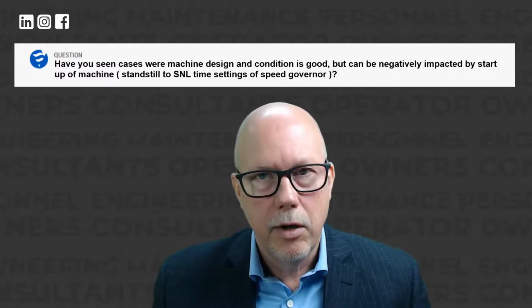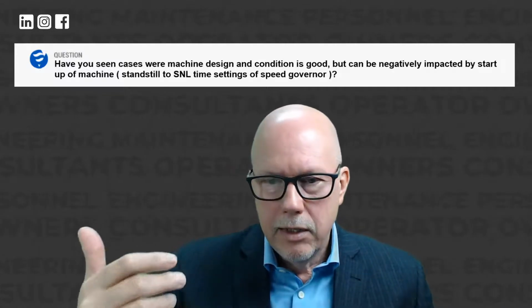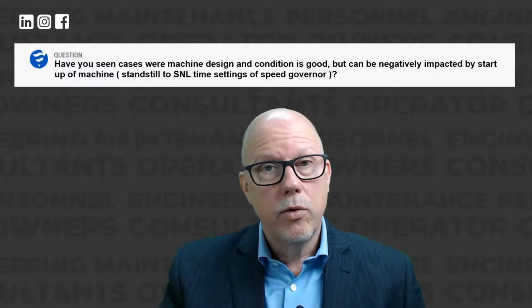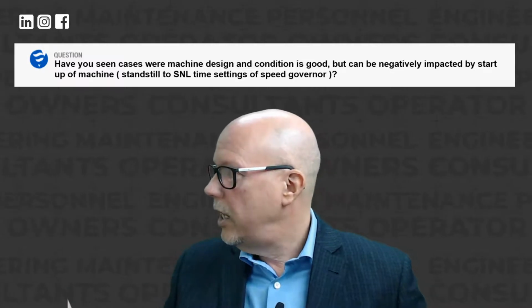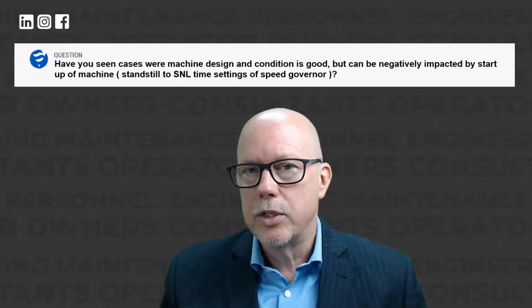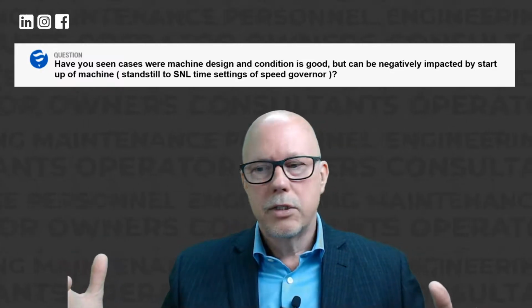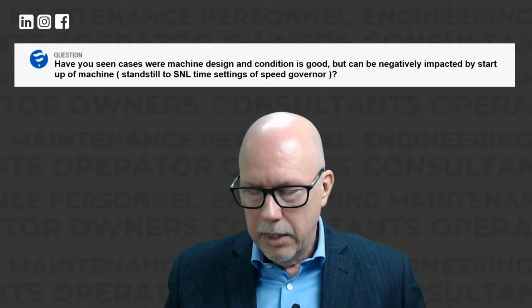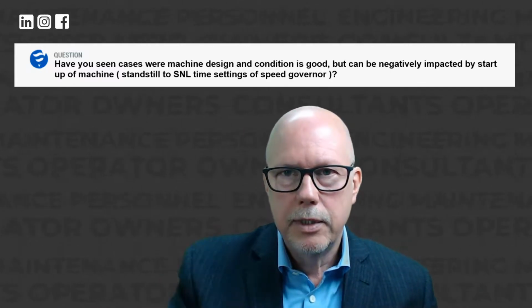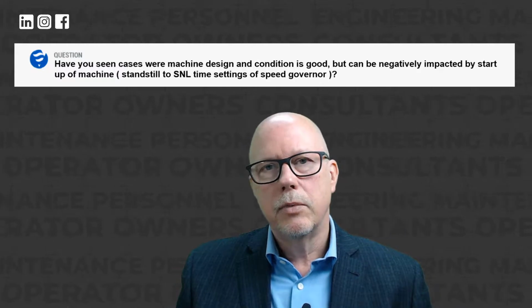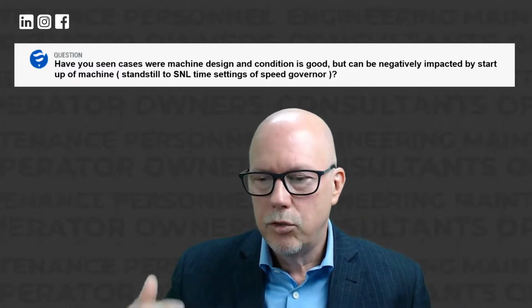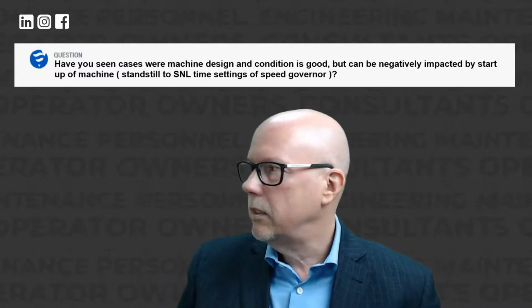So the unit was put through a tremendous amount of stress needlessly. It was just an error. If we hadn't taken the measurements and noticed this, it would have probably gone on unchecked, and eventually they would have had all kinds of rotor issues and wondered what the problem was. The problem was simply the configuration of the startup, the machine accelerated too fast, and that was corrected, and the machines are fine.